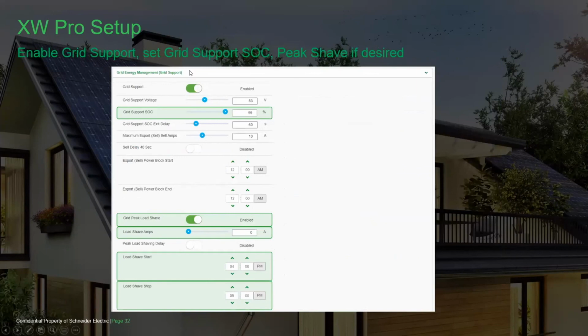Next, you're going to enable grid support, and your grid support SOC determines how full your batteries will remain when you're exporting to the grid. And then when you enter the load shave time period, that dictates how deeply you discharge your batteries down to the recharge SOC limit. Then of course you can set your maximum sell amps here, how much you want to export. And then your sell block is used in case you wanted to export during a certain period of time. You could do that at a certain magnitude.